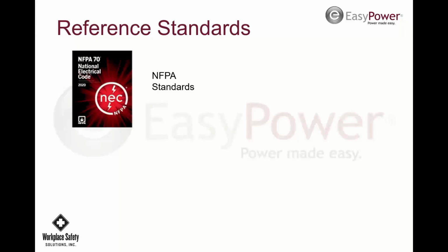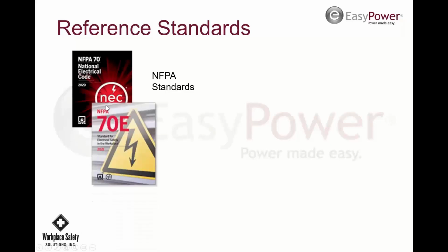As far as reference standards, we have the National Electric Code. It's kind of like the mother of all electrical codes. That started in 1897 when they started having fires with the electrical systems they were installing in New York City and Philadelphia. There were about 6 or 7 different standards back then, and these committees got together and decided on one, which was the National Electrical Code from the National Fire Protection Association. So that's NFPA 70, the National Electric Code. From that, we got 70E.